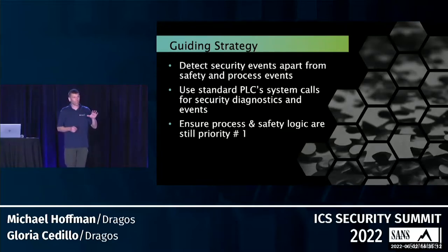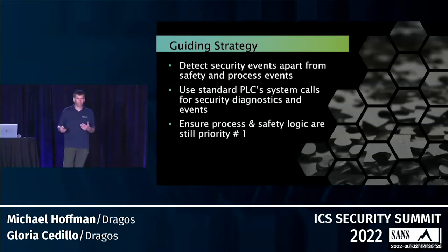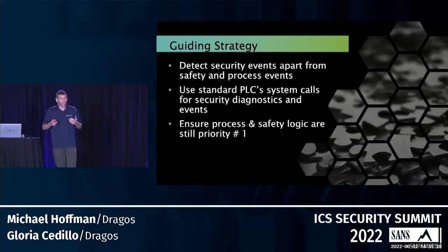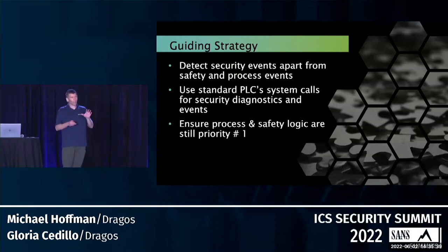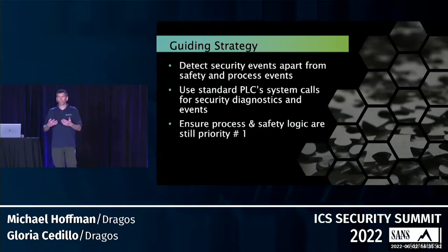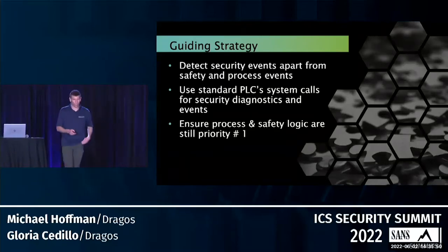The guiding strategy has three key things: leveraging security and detecting security events, but doing it apart from process and safety. Security is extremely important, but just as important is making sure you're detecting process events and safety events separately. Another guiding strategy is using inbuilt capabilities within the device — standard built-in capabilities and standard system calls, like within Rockwell's 'get system value' and those kind of things. Also ensuring that even though we want to add security capability, we're not taxing the device so it can't do its main function, which is process and safety.